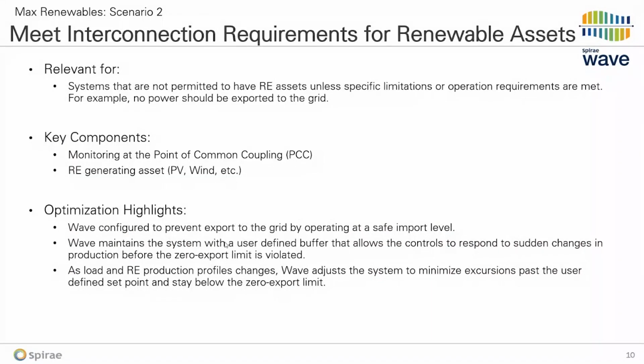For our next scenario, we're going to be looking at how we start adding in renewable energy into our system. So what we'll be looking at is meeting interconnection requirements that might be necessary to satisfy the utility that we're interfacing with, make sure that they're comfortable with the additional technology that we're adding in. Often utilities will want to make sure that these distributed energy resources are not disrupting grid operations, that there's not often a reverse power flow. Zero export is often a requirement that you'll see, where they want to make sure that any excess energy that's being produced by your facility is not flowing back to the grid, creating capacity issues or operational issues or even safety issues for that grid operation.